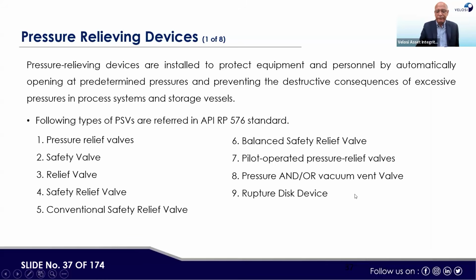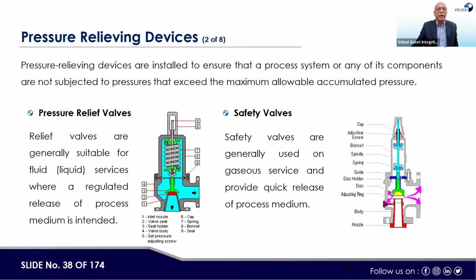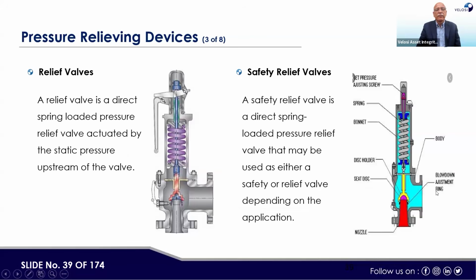If we see them one by one, this is the pressure relief valve. Here is the inlet, there is the outlet. If there is a high pressure, this disc will press against the spring and it will open at a certain set pressure. Similarly, if you see the safety valve, here there is a pressure and this pressure would open this disc to the upper side and then fluid will go to the outlet side. The relief valve is also similar, and the safety relief valve also, there is no major difference. There is an inlet, there is this disc. When the disc is pushed up, fluid will go this side. Same is the case here.